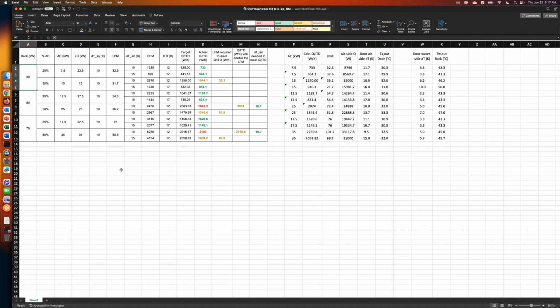We highlighted 30, 50, and 70 kilowatt variants. The 30 kilowatt variant of OpenRack V3 is pretty much POR, and all the documentation should be available through OCP. The 50 kilowatt variant has been proposed through the rack and power stream, looking at 25 kilowatt shelves with 5 kilowatt rectifiers. The 70 kilowatt variant is more future looking; there isn't necessarily a work stream focused on it currently, but we can consider it for pushing density to a really high end.